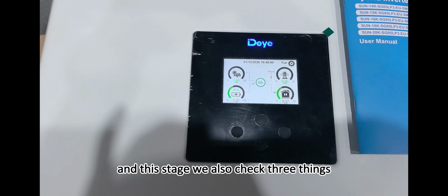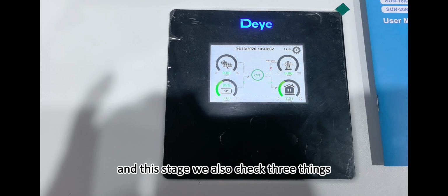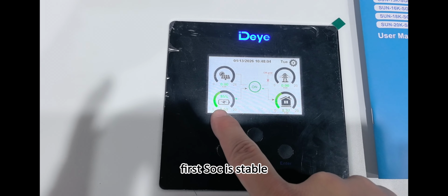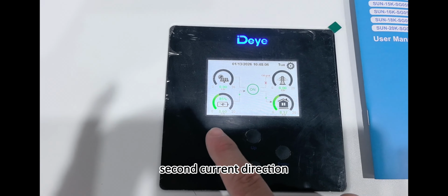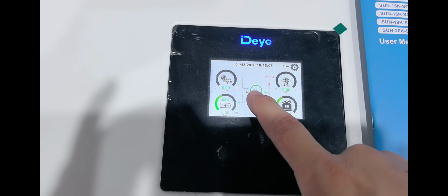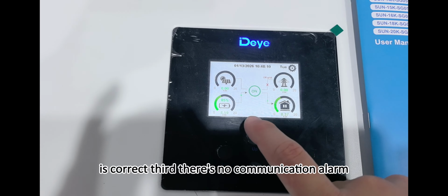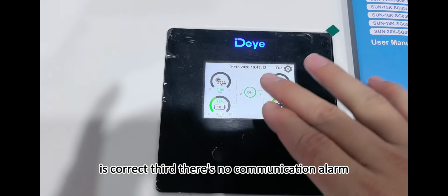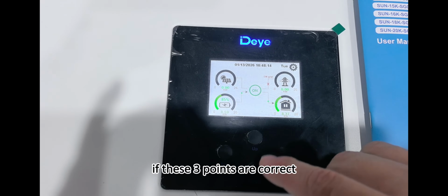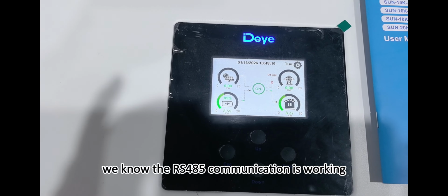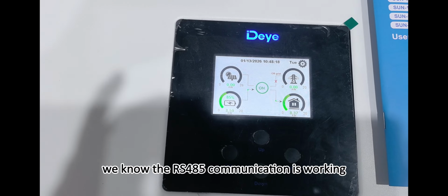At this stage, we also check 3 things. First, SOC is stable. Second, current direction is correct. Third, there is no communication error. If these 3 points are correct, we know the RS485 communication is working properly.